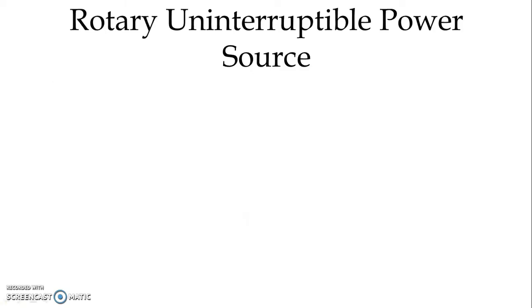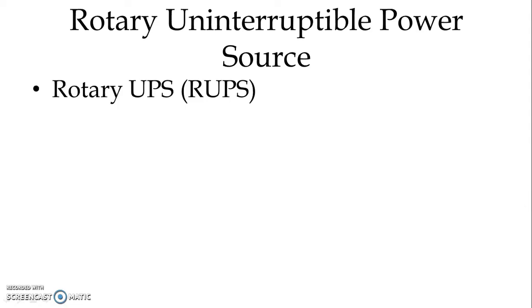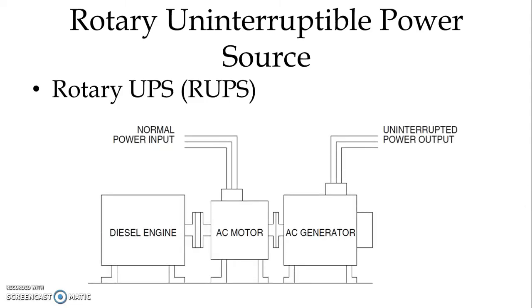In a similar way, we have the rotary uninterruptible power source, that is RUPS. Now we can see that we have an AC motor connected to the normal power system, and we have an AC generator. So the AC motor will act as a prime mover to the AC generator. As long as normal power is available, this AC motor will rotate and act as a prime mover for the AC generator, and the AC generator will generate AC power. Now to make this AC power an uninterrupted power system, we use an additional diesel engine as an alternate source of prime mover.